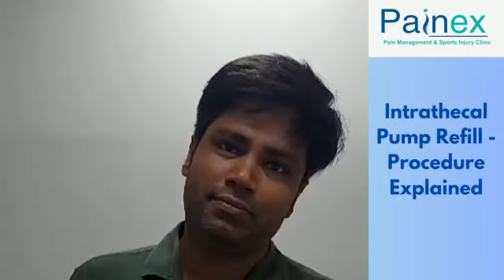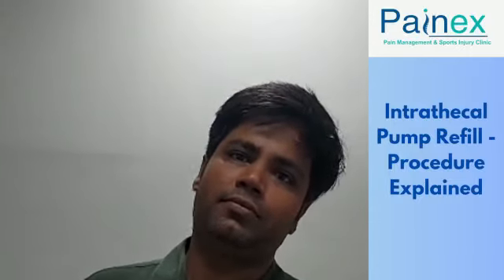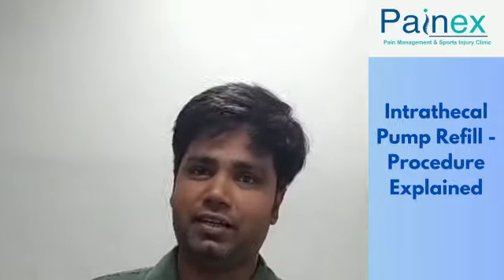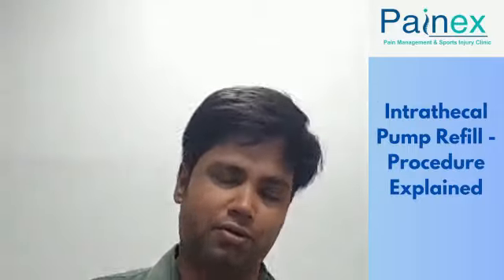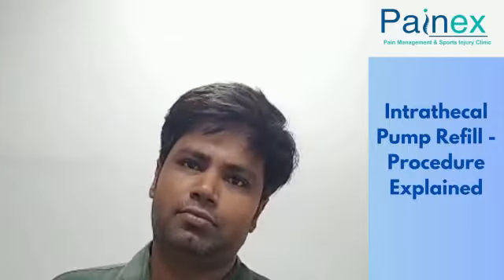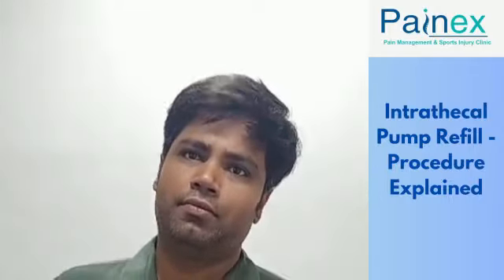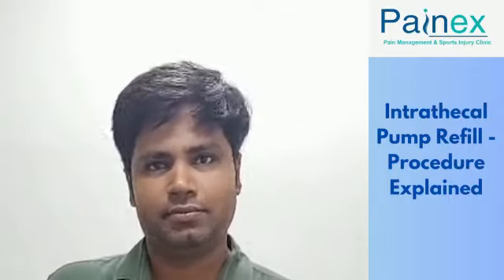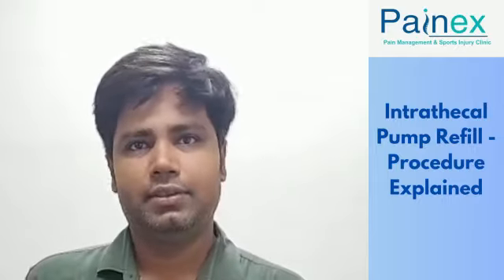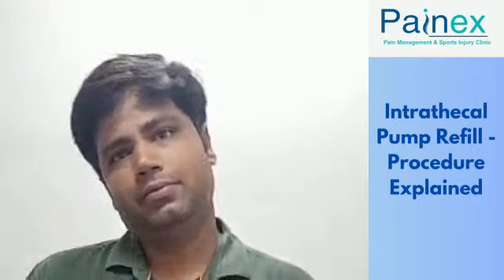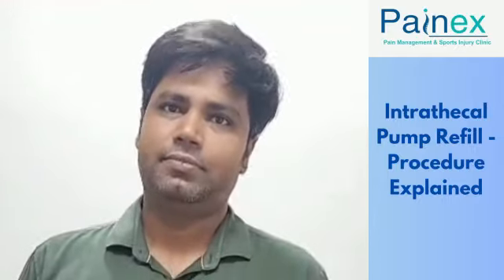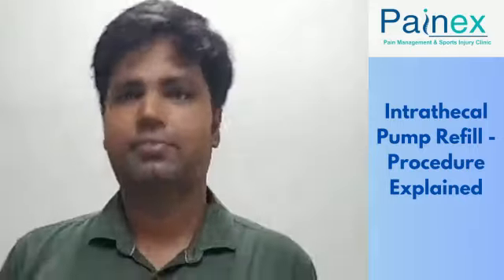While doing the MRI, do we need reprogramming, or can we directly send the patient? No, we have to check if there is any change in parameters or not. So if I schedule an MRI for the patient, we need to inform you as well, and you will come check the relevant parameters, confirm the pump is working normally, and then we send the patient for the MRI. We as a doctor cannot send the patient directly for an MRI without informing the company, right?